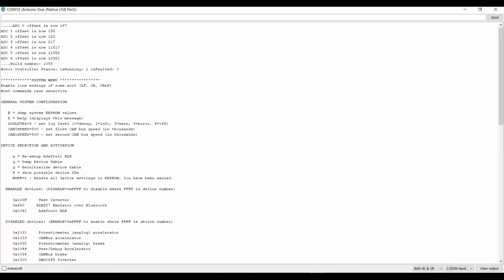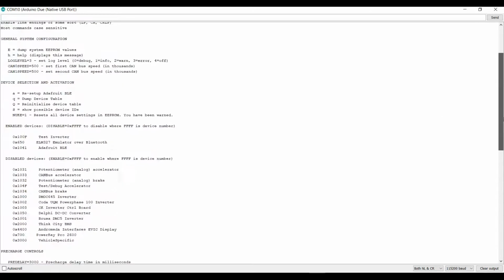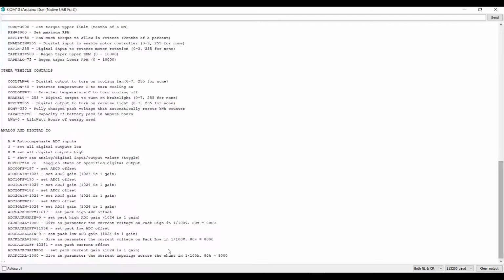Now what we need to do is come down here, and we'll see the commands we need to run. We're going to run the pack low calibration, and we're going to set that to 0. So in addition to running the A to D zeroing, we're telling it that the low value of the battery pack is really 0. This comes through in 1/100th of a volt, so 0 is still 0.